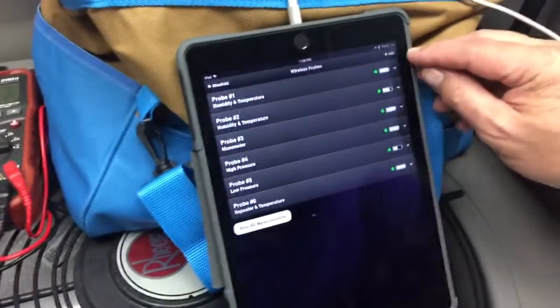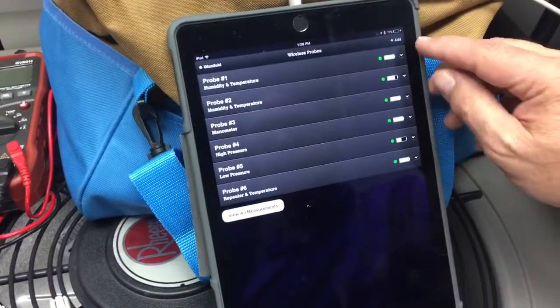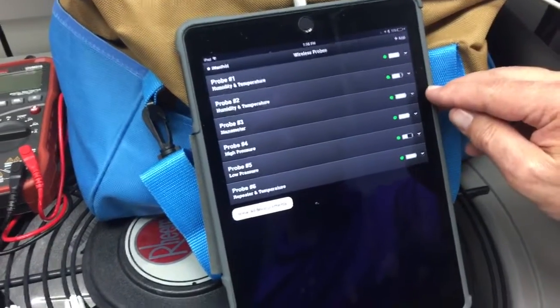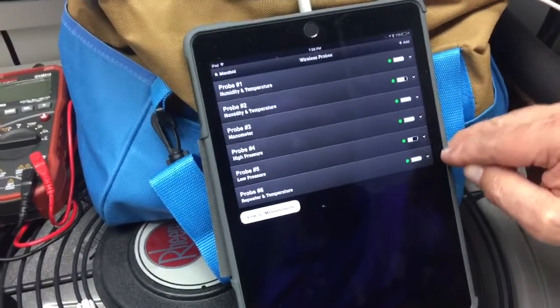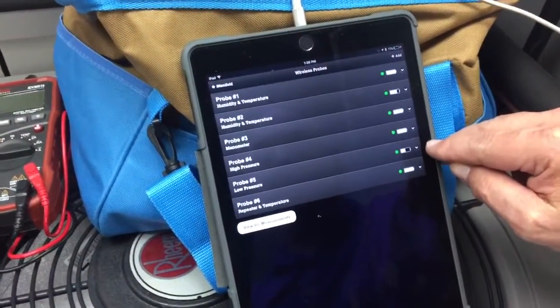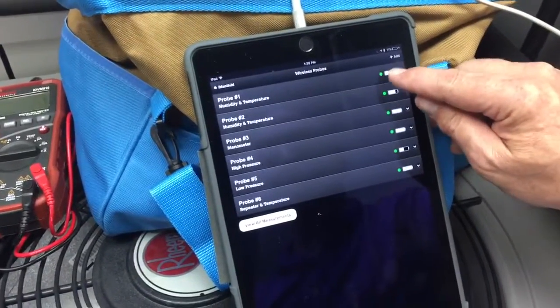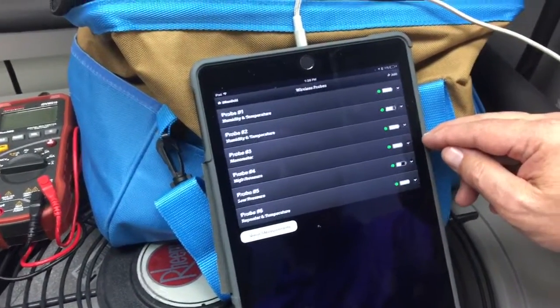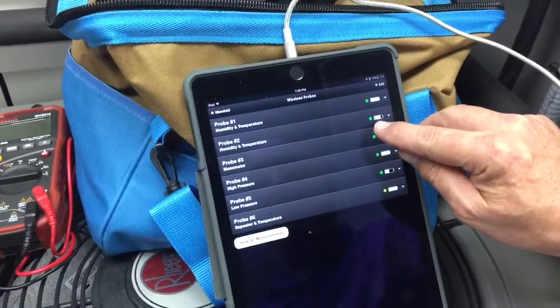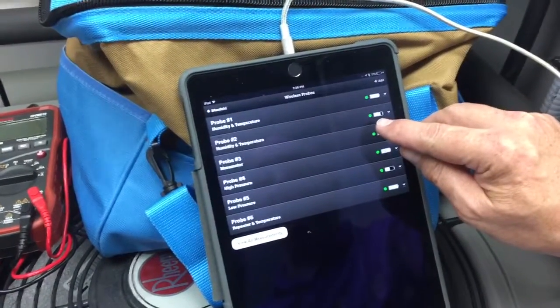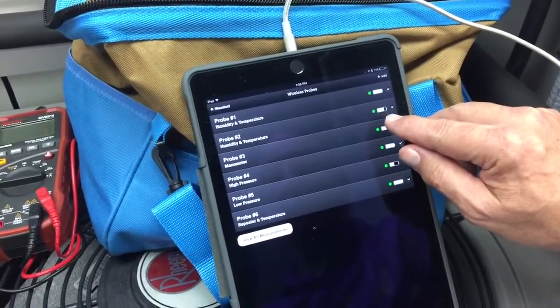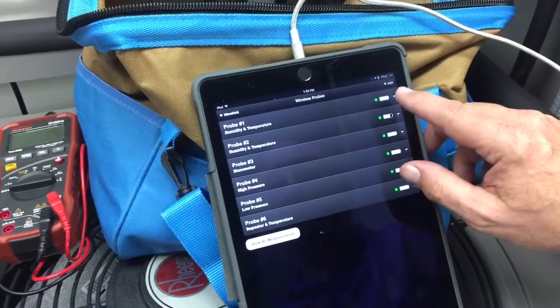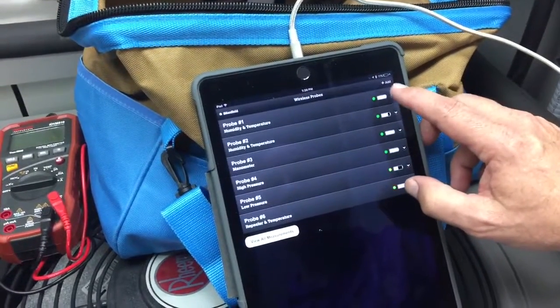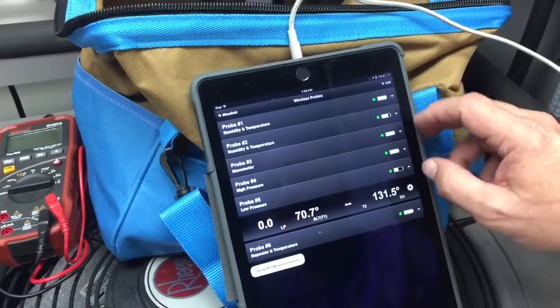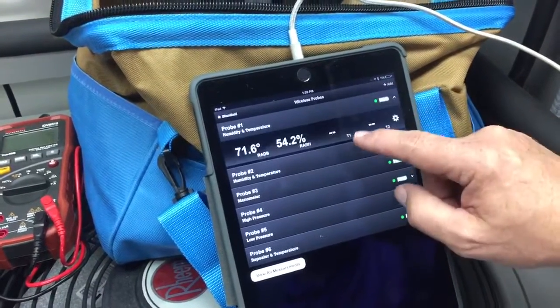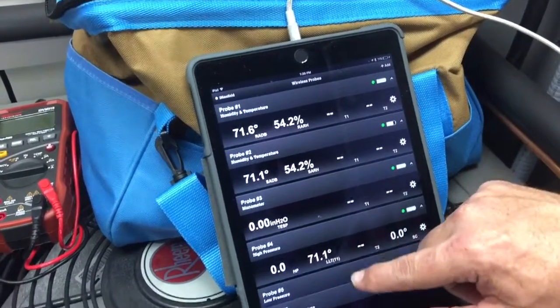Now you'll see all the probes report in: humidity 1, humidity 2, our manometer, our high pressure, our low pressure, and our repeater and temperature. You're also going to see the batteries come in, and indicator lights showing that the probes are communicating with the network. Periodically you might see one turn yellow, and that means it's in the network but simply not sending data. Sometimes if they're not communicating at all, they go red, and that means there's a problem. If you tap on any one of them, you can open them up.